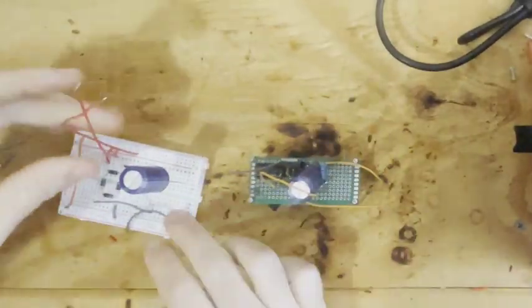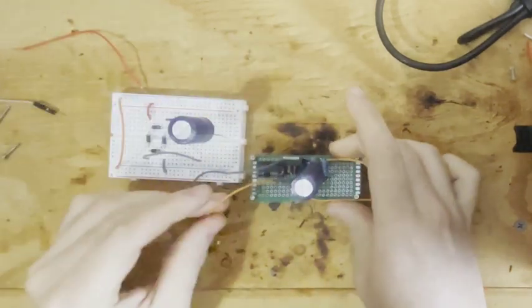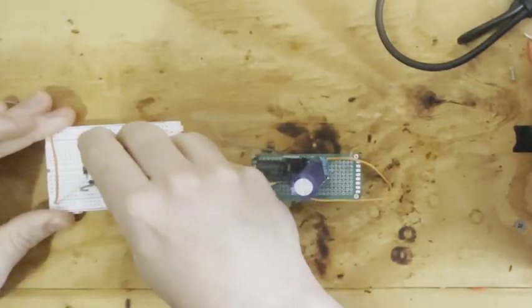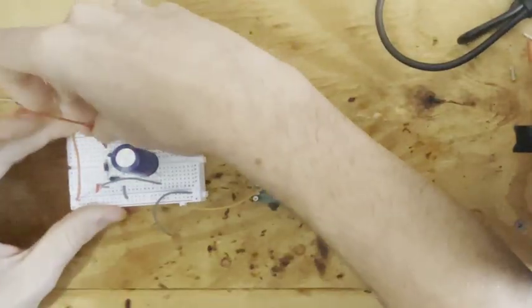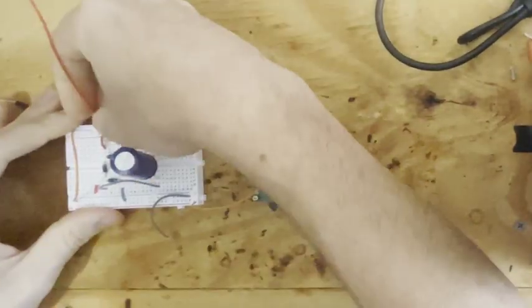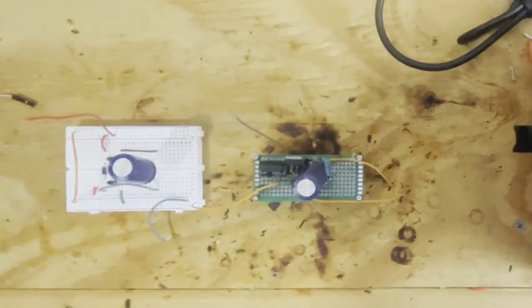The team's initial focus during testing was on establishing the necessary circuitry for the power supply, which included both the rectification stage and voltage regulation stage. The rectification stage was crucial, as conventional voltage regulators require a DC signal for effective regulation, and the embedded components within the smart breaker also necessitate a DC power source.